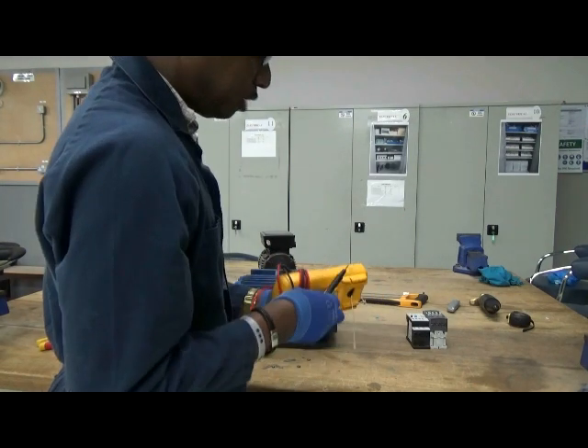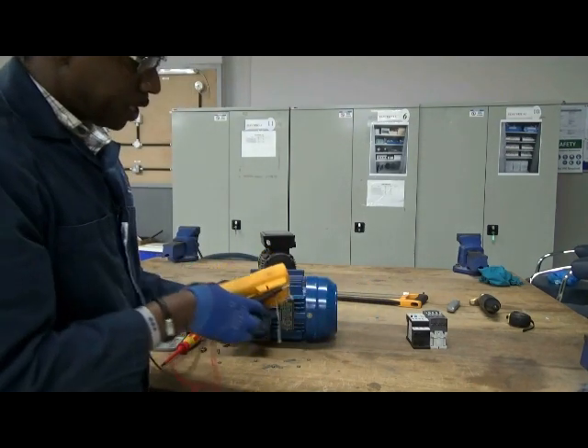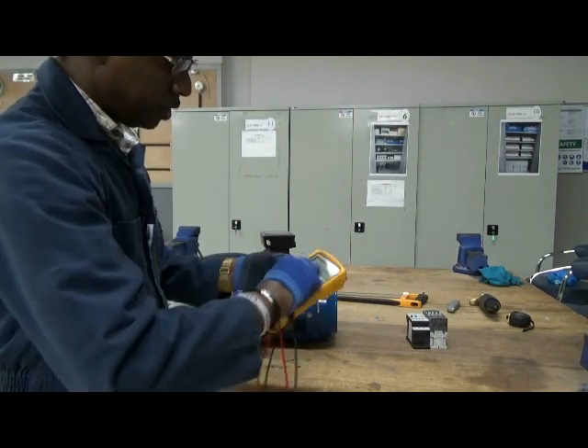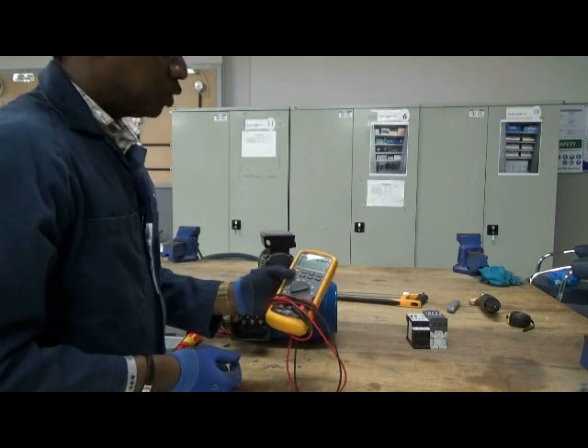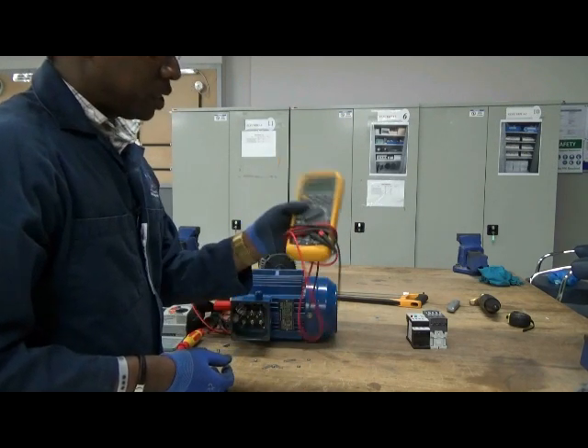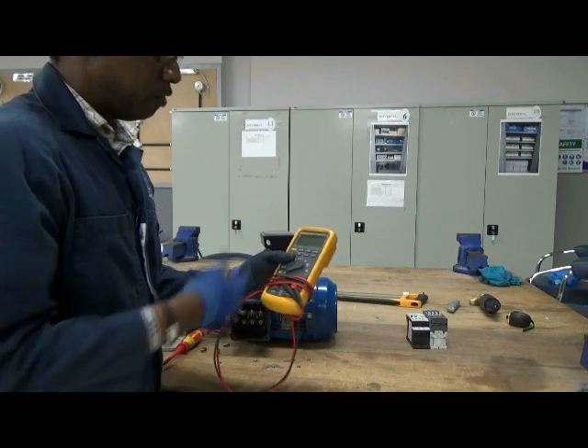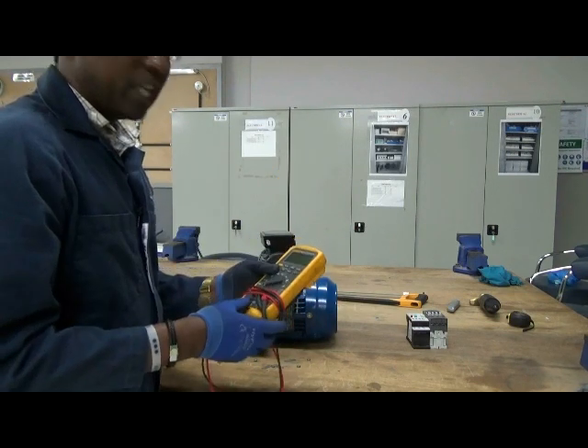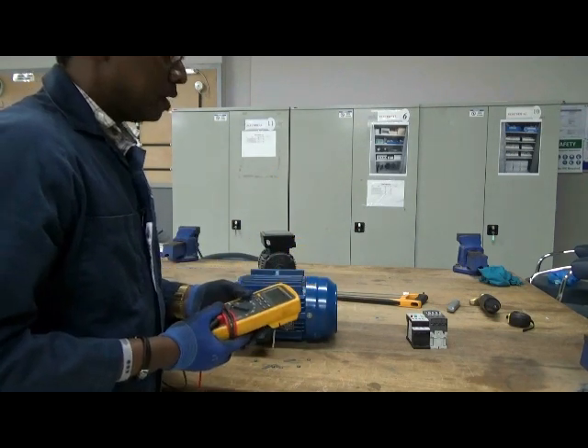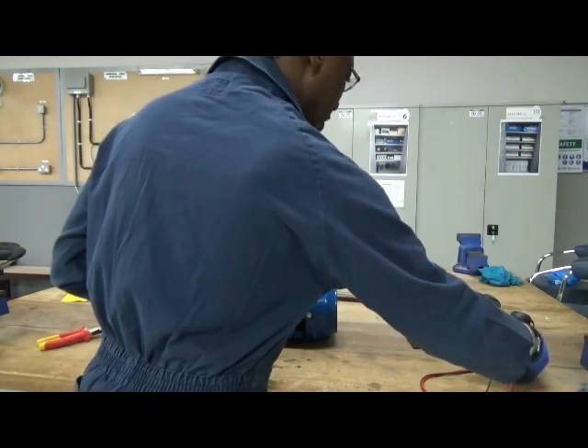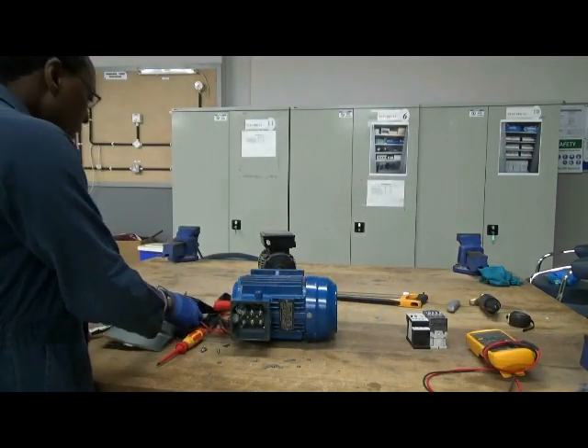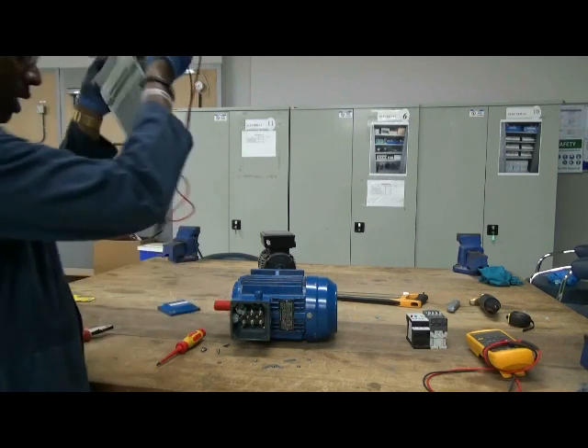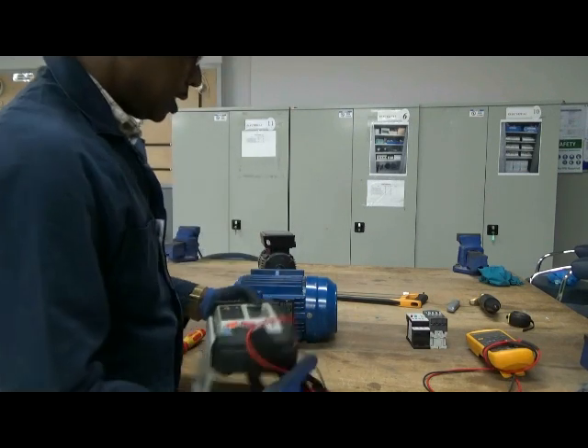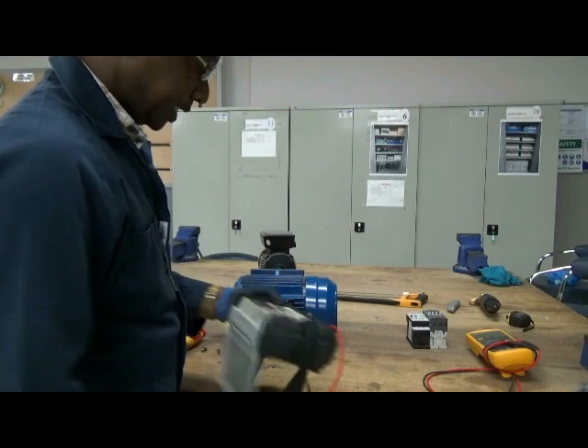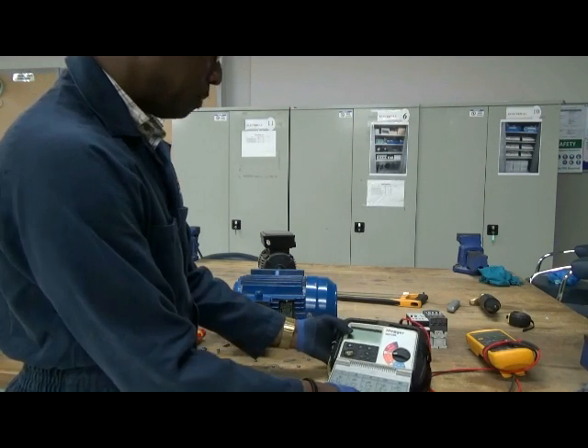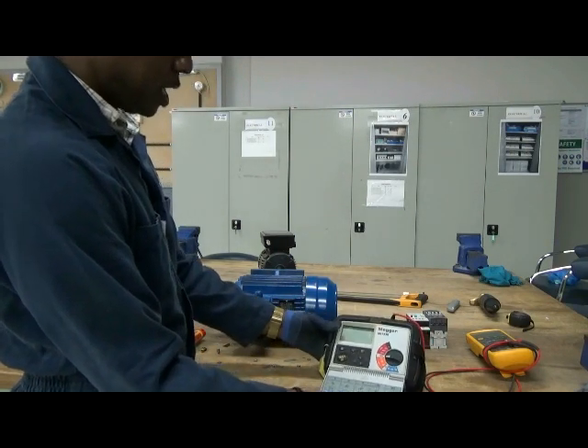Most people would really know what a Megger is, but technically a MEGA is an insulation resistance tester. So I've just finished using my multimeter. What I'm going to do now is to switch it off. I can switch it off to save the batteries, but fortunately with the Fluke type, even if you leave it on, after a few minutes it will switch itself off, thereby saving the batteries of the instrument. Now, this is our insulation resistance tester, like I said, popularly known as a Megger.